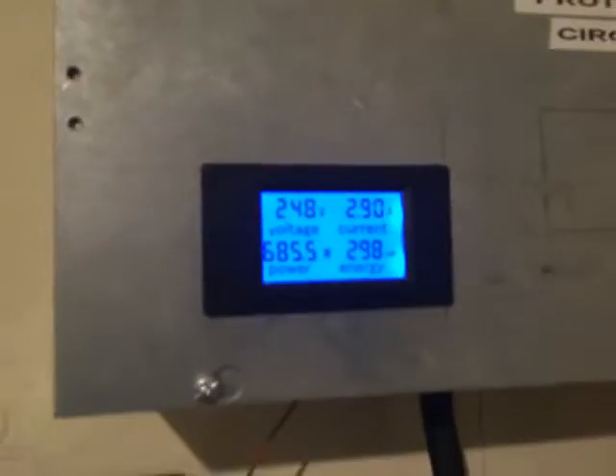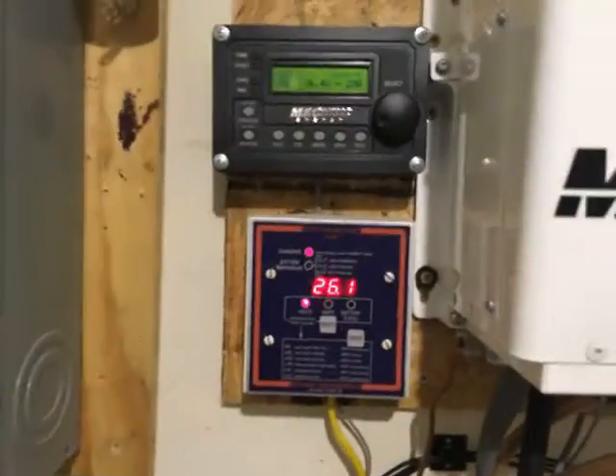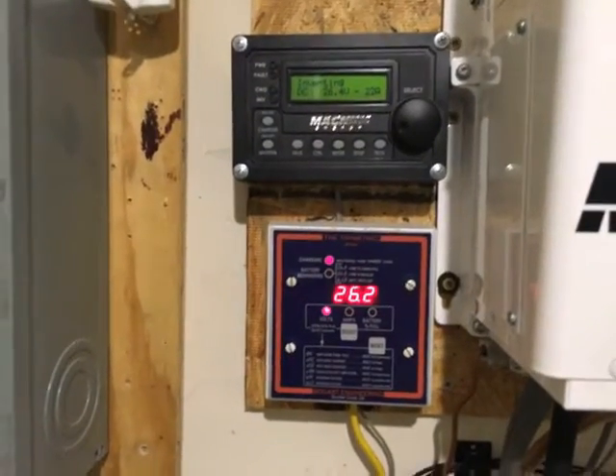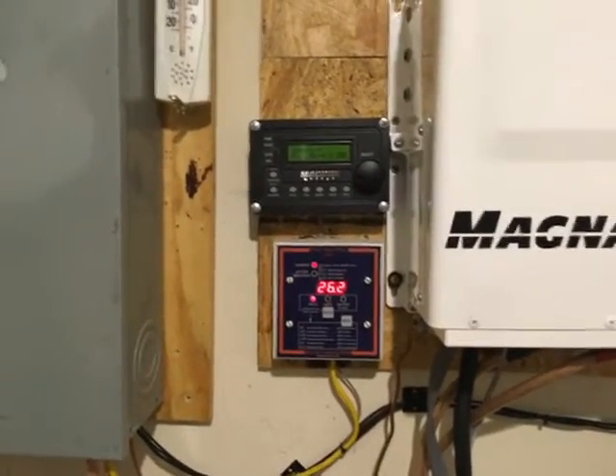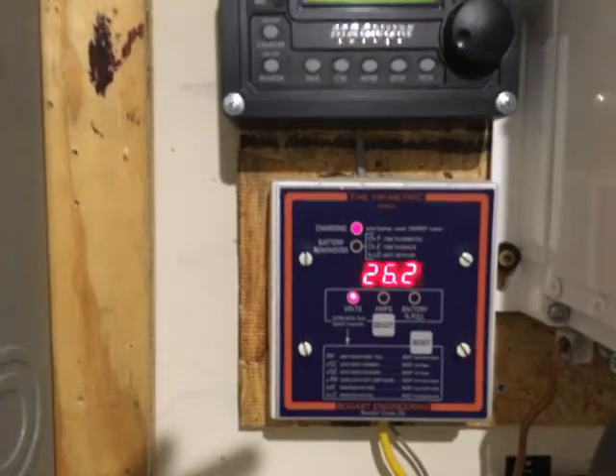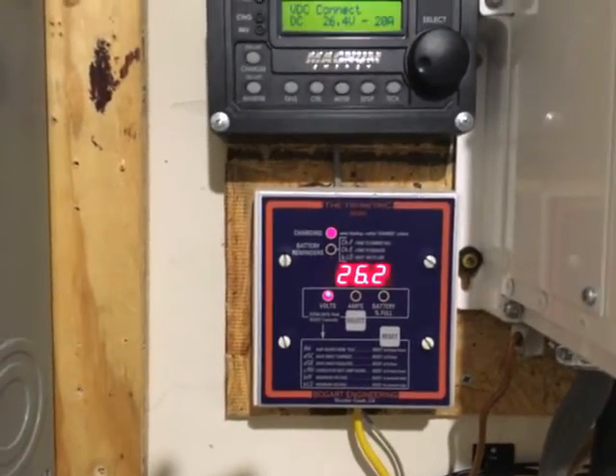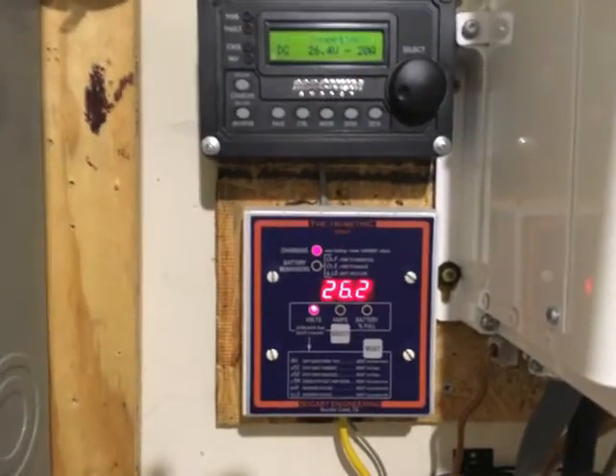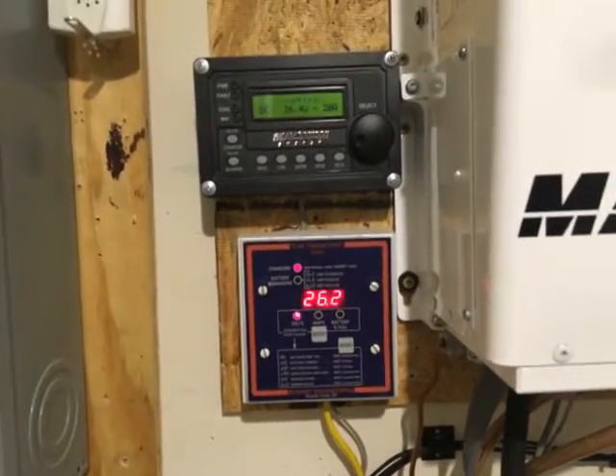I'm already at 26.1 volts and climbing. This is what happens in an AC-coupled system when you don't have enough loads to consume what's coming in. The microgrid concept — you can Google it for more detail — means my 240-volt circuits like the water heater, HVAC, stove, and dryer are still connected to the utility, while all my 120-volt circuits run through my Magnum inverter via a transfer switch shown in previous videos.